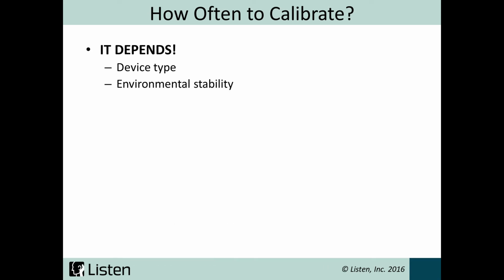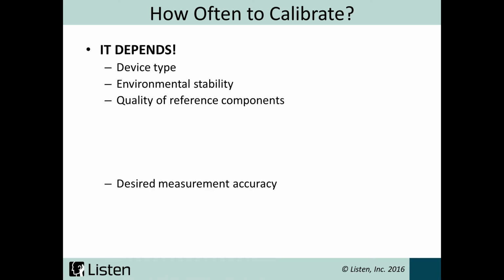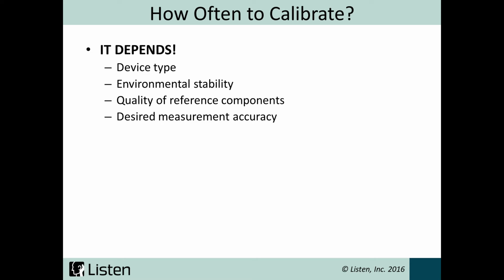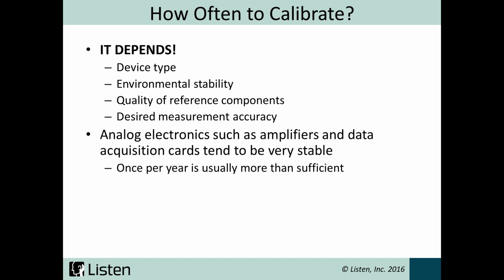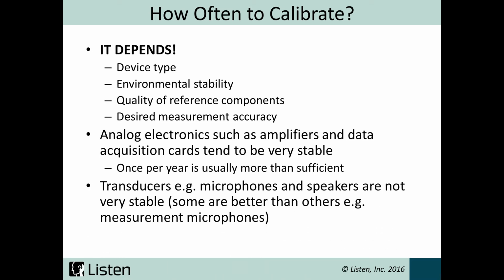One question we often get is how often to calibrate. And unfortunately the answer is always, it depends. The device type, the environment you're working in, your components, your measurement accuracy, all weigh into how often you need to calibrate your own devices. As a rule of thumb, electronics such as amplifiers and acquisition cards and interfaces tend to be very stable. On the other hand, transducers such as microphones and speakers are not very stable.